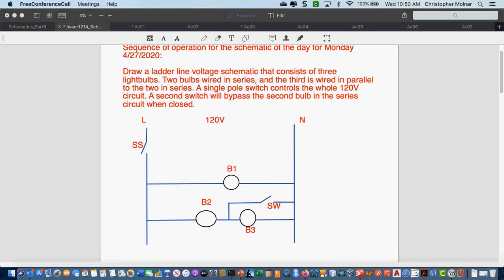So again, we had the bypass. Okay, and it's not used very often in HVAC. Okay, we basically use it in a couple different spots. Sometimes in electric heat, we use it a little bit in a few air conditioning controls, and we use it very heavily in the primary control, which is our safety of the oil burner. We use a bypass. So that's why I wanted to introduce the purpose of the bypass.